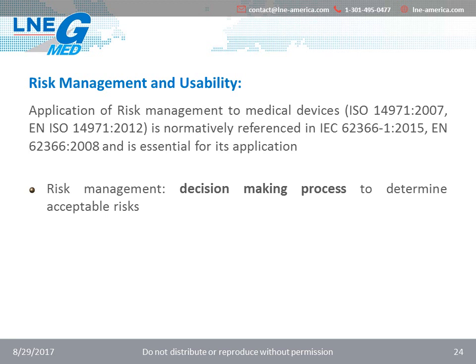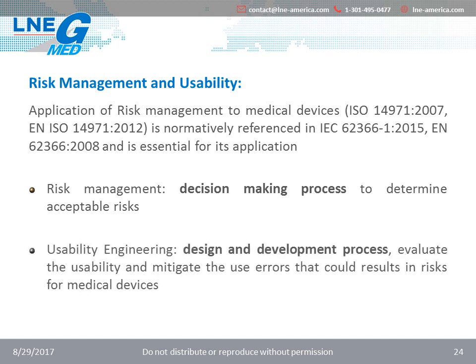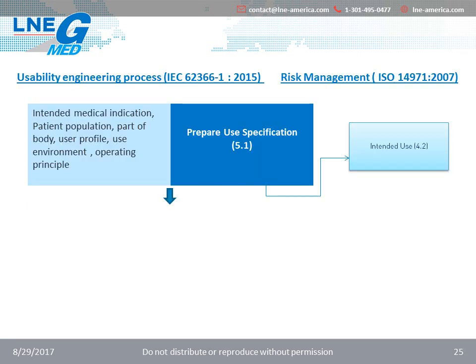Risk management is in fact a decision-making process to determine acceptable risks, and all risks arising from usability have to be evaluated by risk management. However, usability engineering as a design and development process evaluates the usability and mitigates the use errors that could result in risk for medical devices.